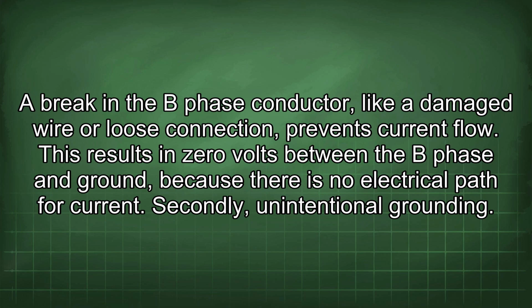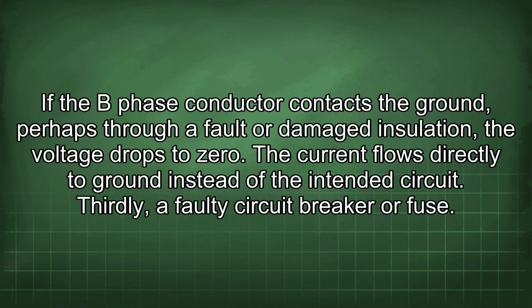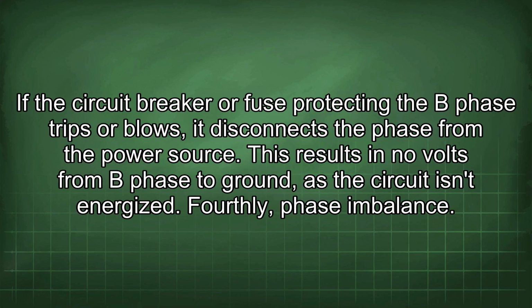Secondly, unintentional grounding. If the B phase conductor contacts the ground, perhaps through a fault or damaged insulation, the voltage drops to 0. The current flows directly to ground instead of the intended circuit. Thirdly, a faulty circuit breaker or fuse. If the circuit breaker or fuse protecting the B phase trips or blows, it disconnects the phase from the power source. This results in no volts from B phase to ground, as the circuit isn't energized.